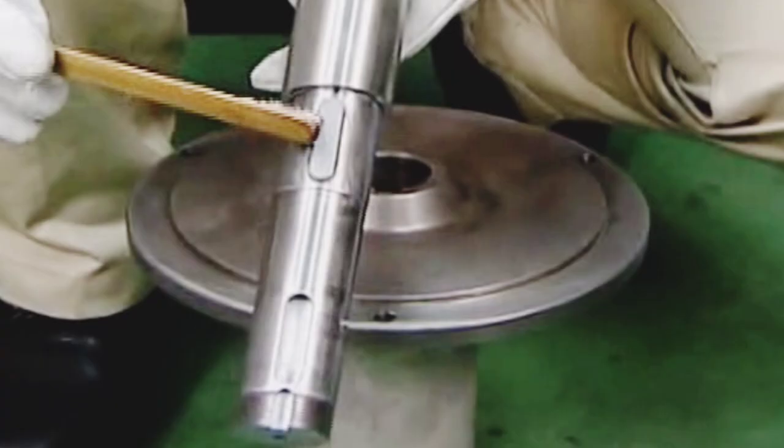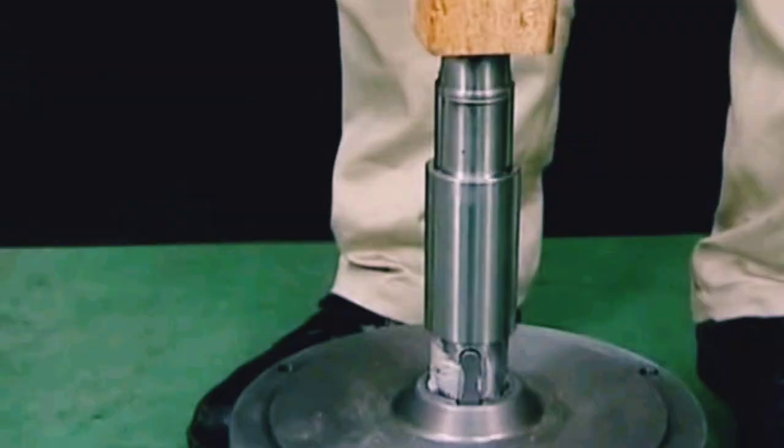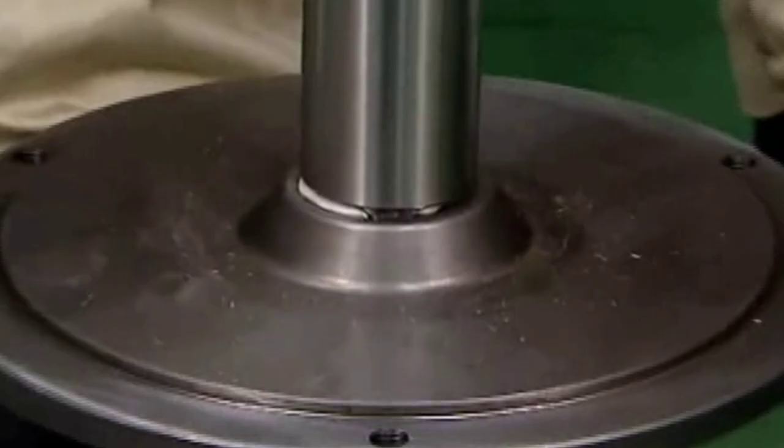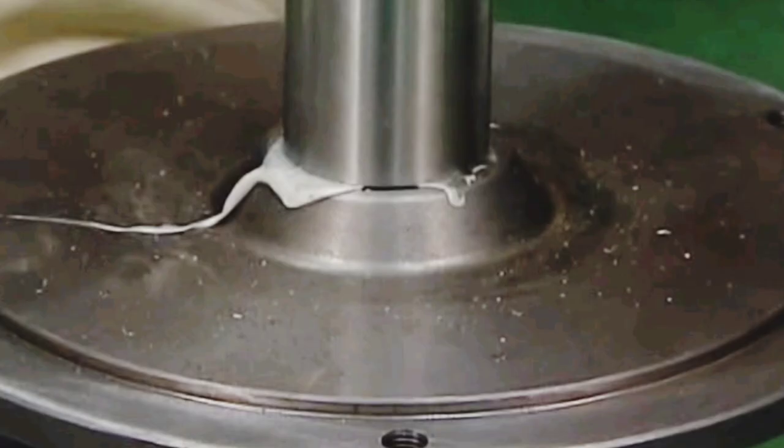Lubricate the engagement part and the line with the key. Then from the pump side, tap the horizontal shaft using the wooden slab or copper hammer. When the gearbox is completely mounted to the horizontal shaft, set the horizontal shaft to the vise.